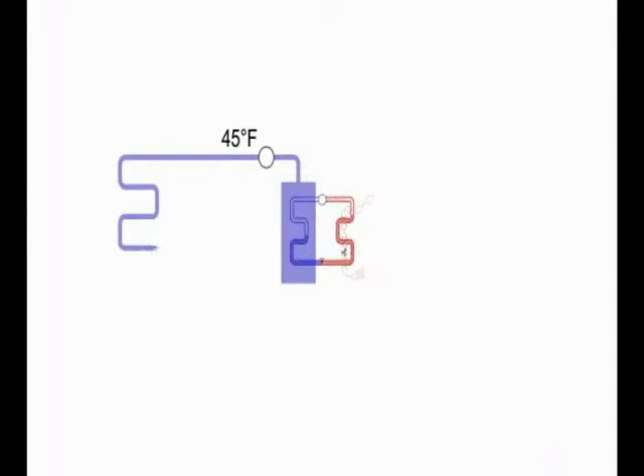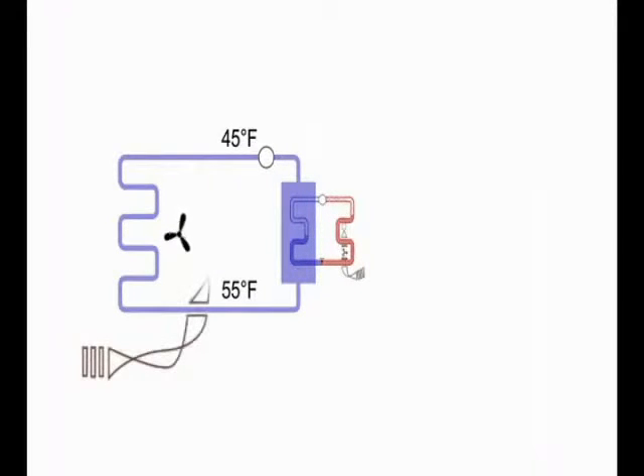In this regime, pumps carry water chilled on the evaporator side, which is to say the cold side of the compression refrigeration loop, to sometimes distant air handling units. The air handling unit then blows air across coils of chilled water rather than coils of chilled coolant.